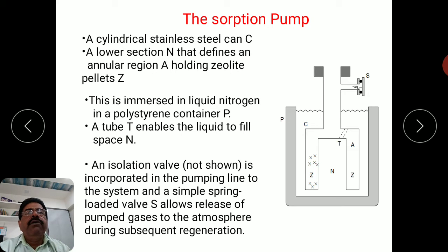Earlier I also defined the process of regeneration. What is regeneration? Whenever any cryo pump continuously pumps gas molecules, whatever the mechanism involved, maybe a condensing surface in a cryocondensation process, that surface may get saturated. That means there will be no further space available for adsorbing the gas molecules. In this case, further pumping will stop. So what is needed is that you need to regenerate, that means you have to remove the earlier gases.